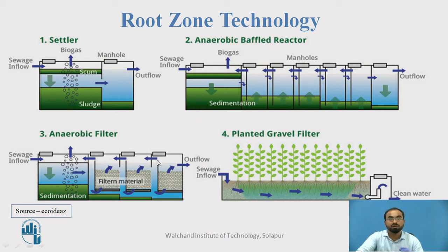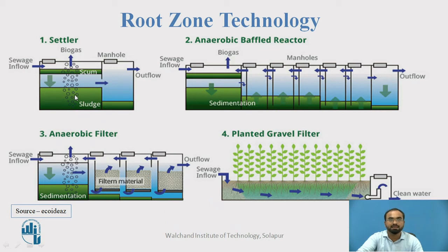There is a four-compartment method being used. The first is the settler, in which the influent enters a biodigester where no oxygen is present, so it uses an anaerobic method for treatment. The scum present above is taken out, the wastewater with large amounts of organic matter is treated anaerobically, and sludge is produced — it acts as a septic tank. The effluent supernatant is taken out and shifted to the second compartment, while the sludge settled at the bottom is disposed of.